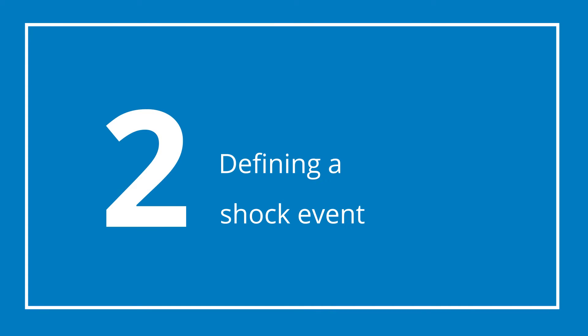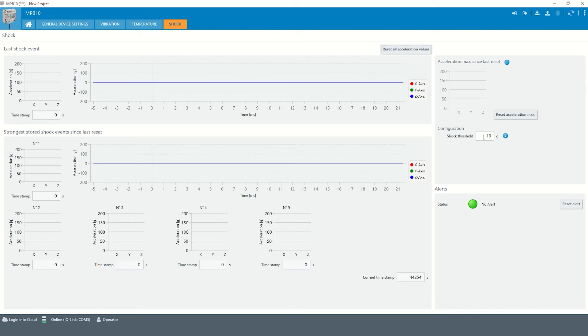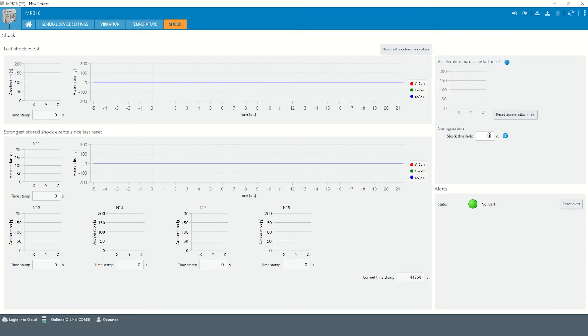Chapter 2: Define a shock event. The monitoring of the maximum acceleration is event-driven. Data is only recorded if the acceleration has exceeded an adjustable shock threshold. Per default, the threshold is set to 10 g.